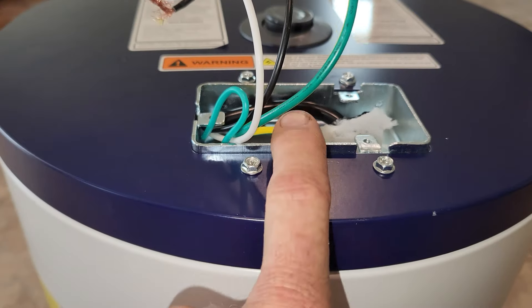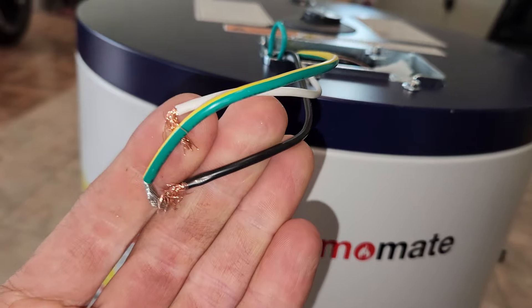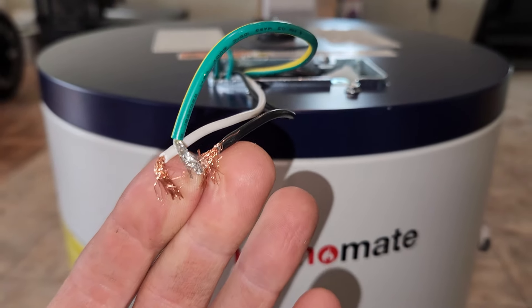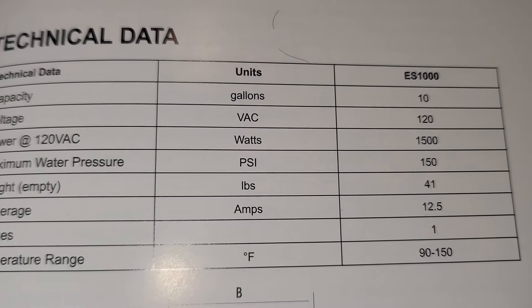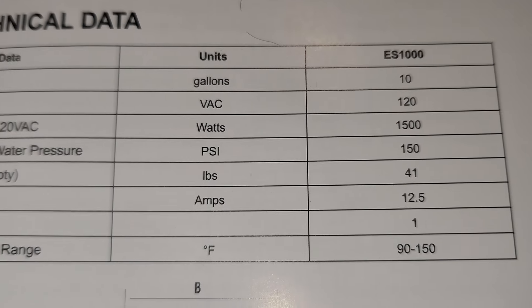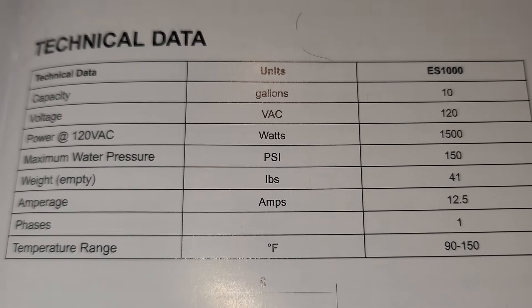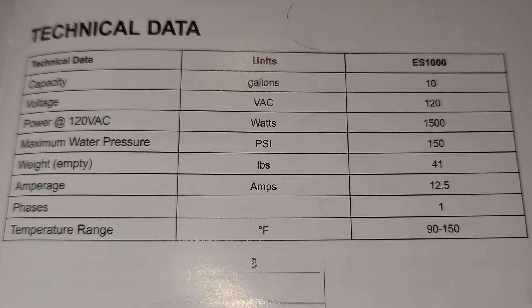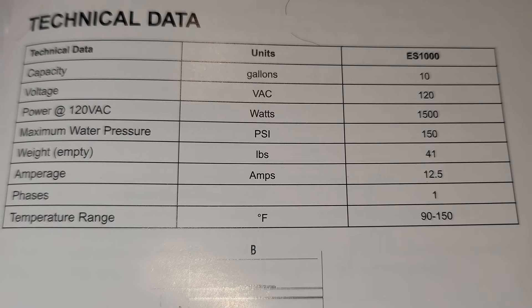On the top, underneath the cover plate, you'll find your connections, which you'll have to either hardwire in or wire a plug, which I will do. What's nice about this unit is it is 120 volts. From the specs: voltage is 120 volts, watts are 1,500, 10-gallon amps is 12.5, and it weighs 41 pounds. Maximum water pressure is 150 PSI, and you can go from 90 to 150 degrees Fahrenheit.